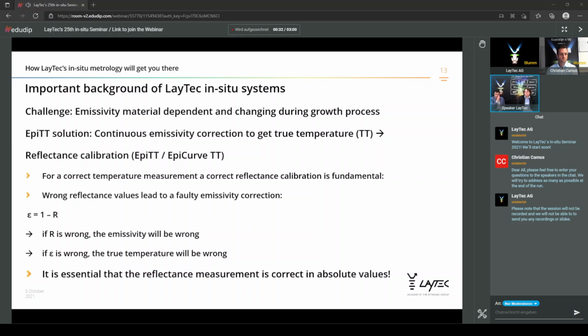So the EpiT2 solution, and this is valid for the EpiCurve as well, is a continuous emissivity correction to get the true temperature. To get there, you need, at the same time and at the same wavelengths, a reflectance measurement, and the reflectance has to be calibrated as well. This is very fundamental to get the correct temperature value, which means, on the other hand, if you do it in the wrong way, or it's not done properly, you will have a faulty emissivity correction, since the emissivity is 1 minus R, so 1 minus reflectance, so it has a direct impact on the emissivity correction.